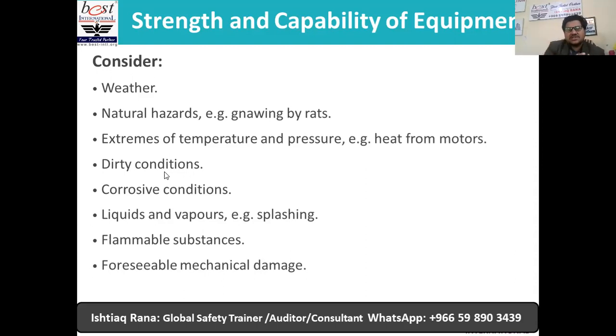Along with humid kinds of environment, so humidity plus dust, and if some oil vapors are also coming from the machine, then that would be a more terrible accumulation of dust. So dirty conditions are not acceptable, and corrosive conditions, liquids and vapors like splashing and flammable substances, foreseeable mechanical damage. So before you select any equipment, make sure it is very strong and capable in these conditions.